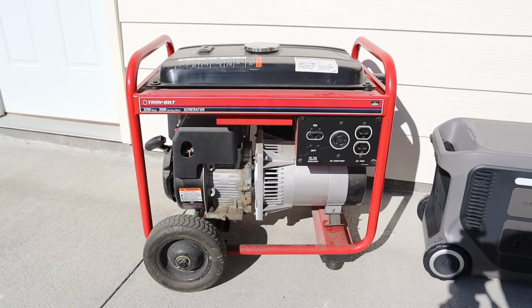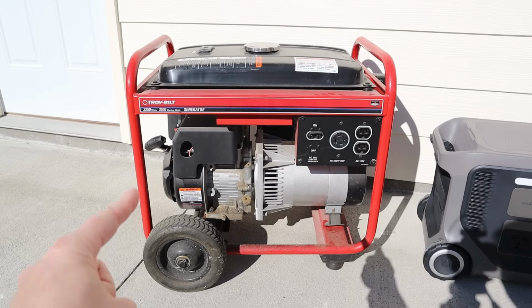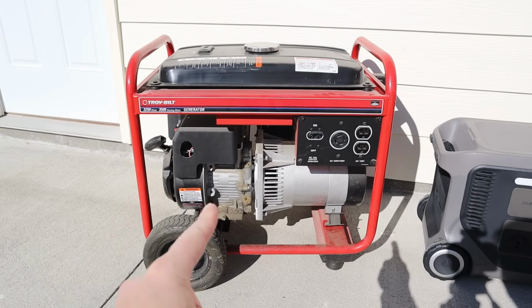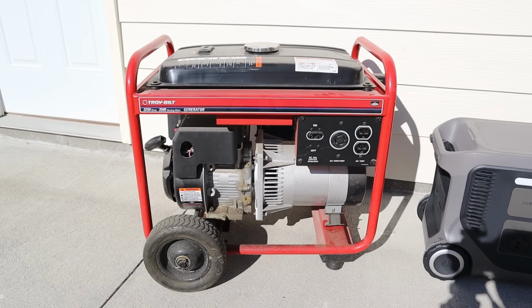To kick off our testing, we're starting with the traditional, non-inverter generator. This is from Troy-Bilt, rated for 3,250 watts continuous output. I've heard these generators put out dirty power, so I'm curious what type of output we get. One downside is the engine is directly connected to the generator output, so if the engine RPM drops, so does your voltage and hertz output. This should be interesting.